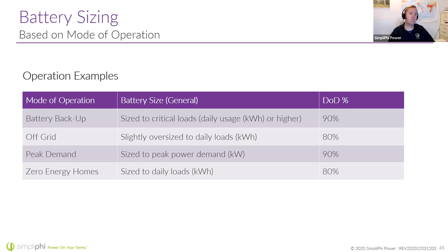When it comes to sizing the battery for power throughput, always size your battery bank to twice the inverter's output capability. Here's my example: an 8,000 watt Radian. If that Radian is ever called upon to provide all 8,000 watts, I want to be sure the battery bank is at least 16 kilowatt hours in size, so the batteries are never called upon to discharge or charge faster than they are capable of handling continuously.